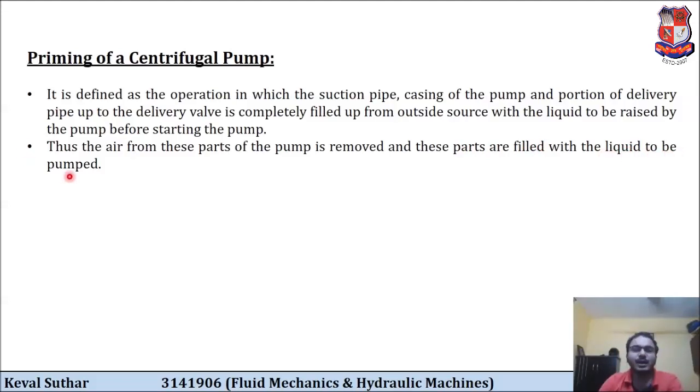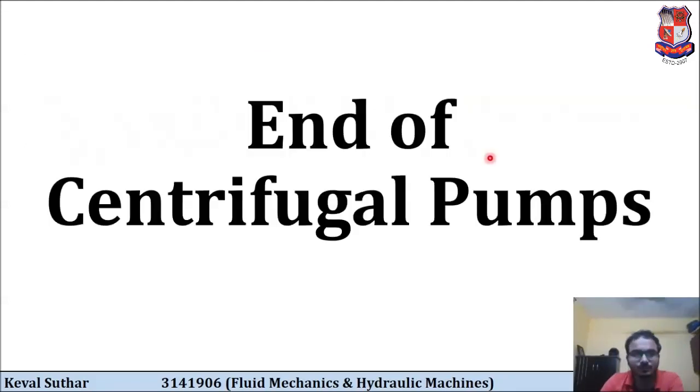These parts are filled with the liquid to be pumped. What happens exactly is that if the pump has been idle for a long time, then air will be trapped inside and it will prevent the starting of the pump. So for that purpose, we add the liquid which is going to be pumped initially by some other means, maybe manually or by some device, so that air can be replaced by the liquid which is going to be pumped.